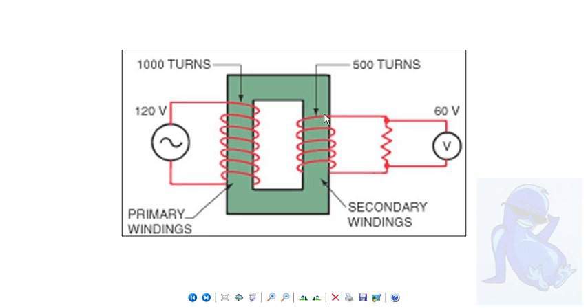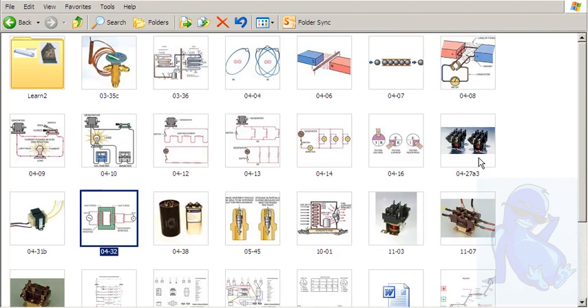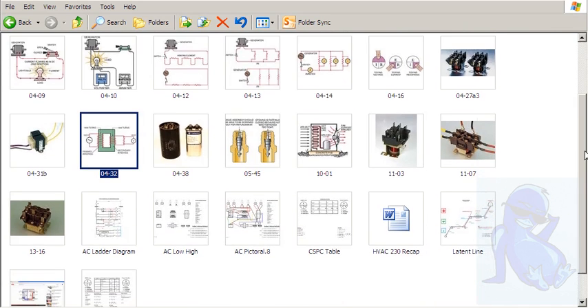On the other side you have another wire wrapped. You'll notice on this one it's 1,000 turns, and on this side is 500 turns. And with that ratio, 2 to 1, you're going to be stepping down the voltage from 120 volts to 60 volts. Now a lot of step down transformers that we use for HVAC, they're 5 to 1. So you'll step down 120 volts down to 24.